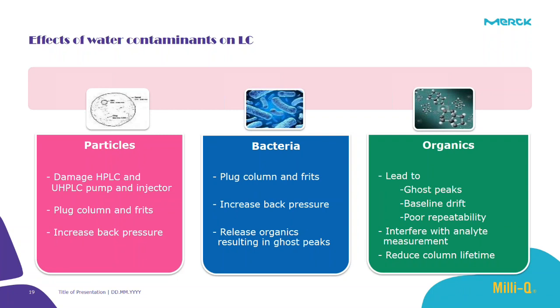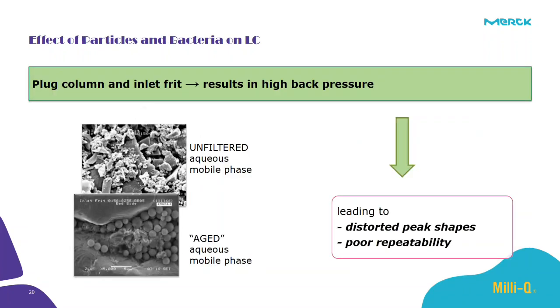Second contaminant is bacteria. The bacteria can plug the column and frits. It can increase the back pressure as well. It can release organics resulting in ghost peaks. Third contaminant is organics, which may lead to ghost peaks, baseline drift, poor repeatability, and interfere with the analyte measurement, and for sure will reduce the column lifetime.